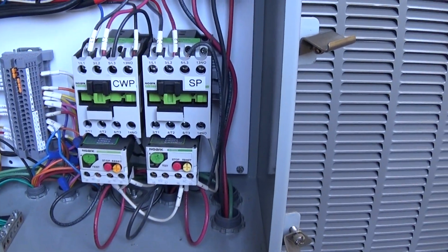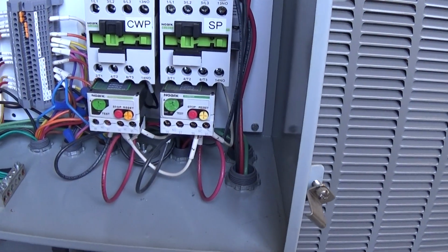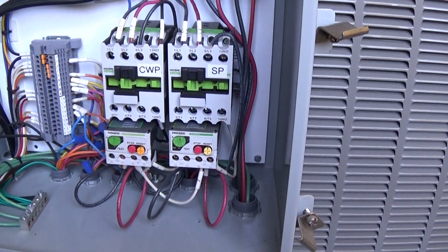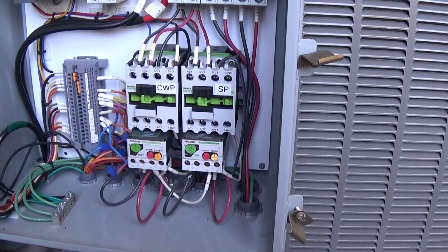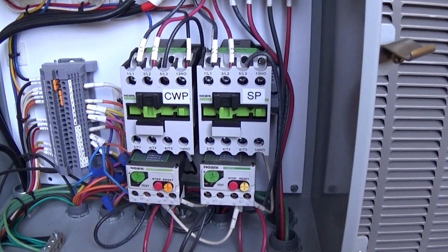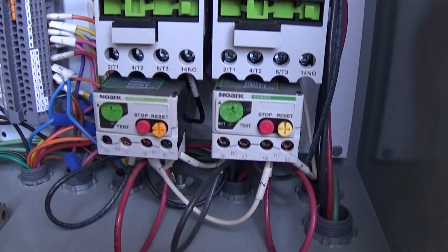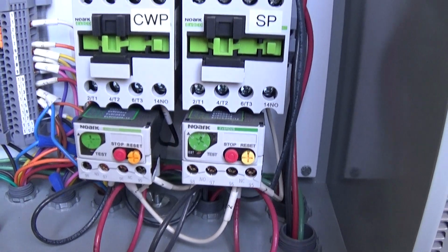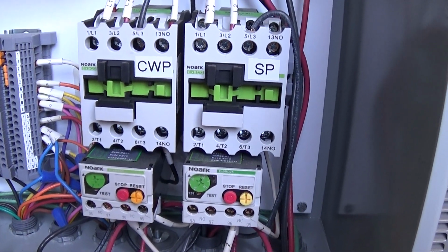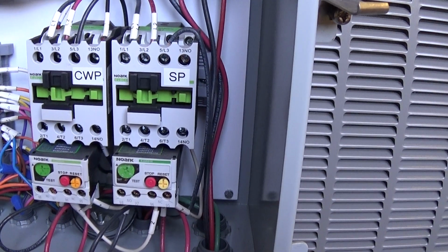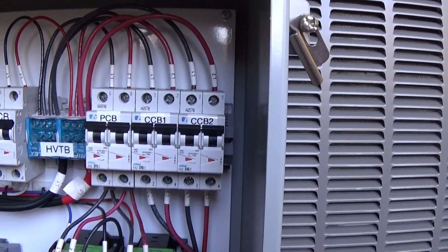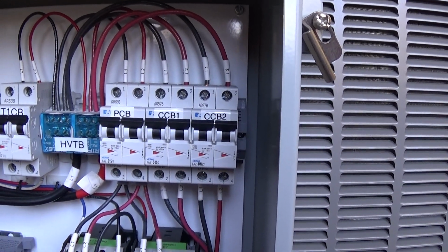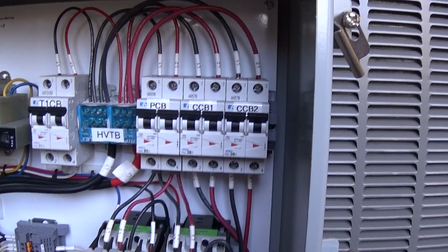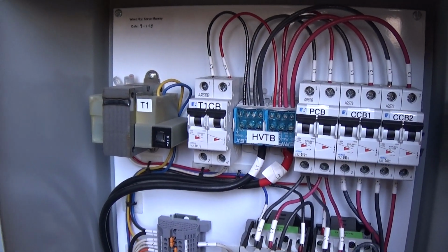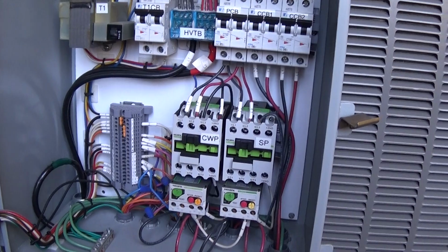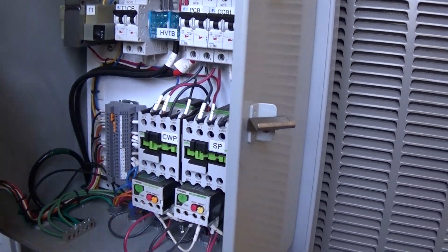That's your contactors and overloads. Actually, it's kind of nice because we have overloads for each pump. Some chillers just rely on the thermal overload of the pump itself. So these are pre-adjusted. That's your contactor and an adjustable resettable overload for the chilled water pump and the supply pump. And then these are our breakers for the compressor and the fans, controller transformers there. I really don't have to touch anything in here upon initial startup.